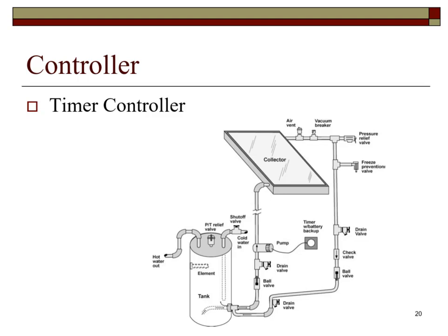The timer systems could conceivably operate during rain or overcast conditions, so care must be taken to ensure the proper supply and return lines to the collector are located near the bottom of the storage tank. Therefore, if the pump operates during a cloudy day, only a small amount of the water at the very bottom of the tank will be circulated through the collector. This prevents potential major tank heat loss.